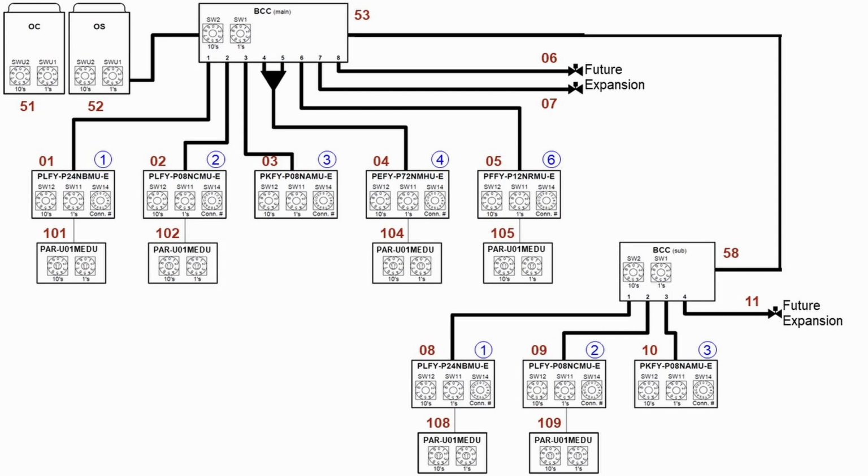If you were to address these incorrectly, for instance, let's say that indoor unit 1, we had set the port assignment to 2, and indoor unit 2, we set the port assignment to 1. So when indoor unit 1 is calling for heating or cooling, it's sending refrigerant to indoor unit 2. When indoor unit 2 is calling for heating or cooling, it's sending refrigerant to indoor unit 1. Therefore, neither of them would be able to be controlled correctly.